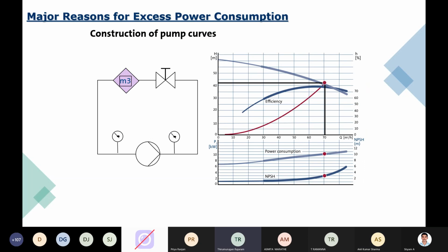So let me take a simple example here. What you have is a simple small P&ID diagram, where you have a pump. It is getting into a machine kind of situation. It is a closed loop. And you have a throttle valve on the discharge side. So you have a suction, a discharge, and some gauges to measure your suction and discharge pressure. And this is the performance characteristic of any centrifugal pump. What is plotted in the curve is flow versus head. You have the flow on the x-axis, head on the y-axis, and the efficiency of the pump on the y-axis on this side.